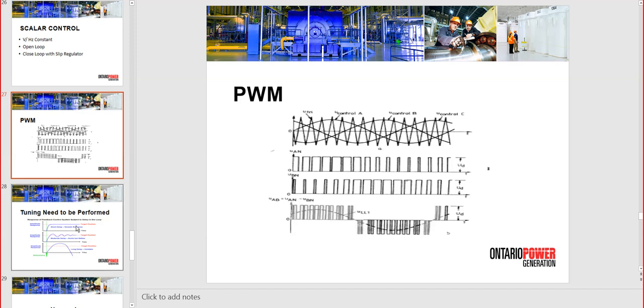Now the motors that are running with VFDs, you need to order that motor as inverter rated, because they are designed as such, they can take these harmonics generated and not suffer too much, because they have reinforced insulation on the first few turns. On top of that, if you want to get lower harmonics in the motor, you can also use the Belden cables, that are yellow jacketed cable with low capacitance, and filters.